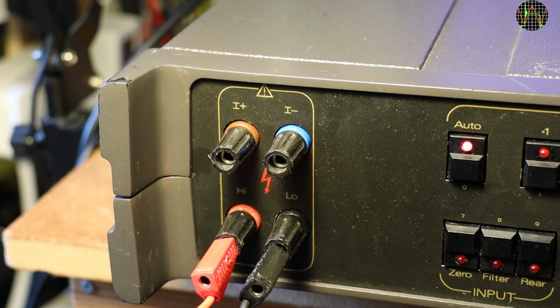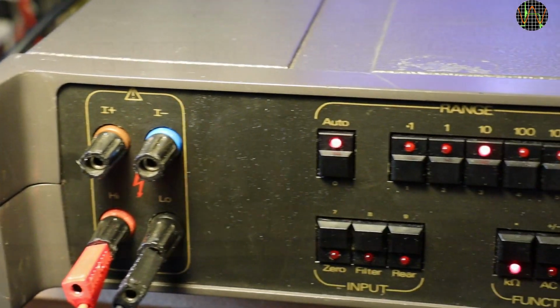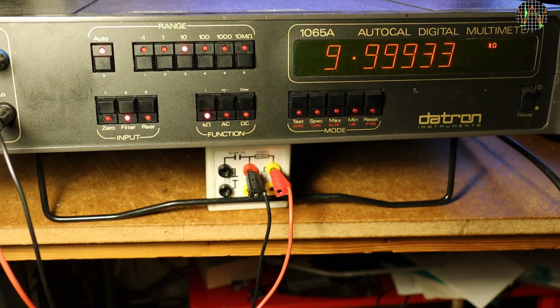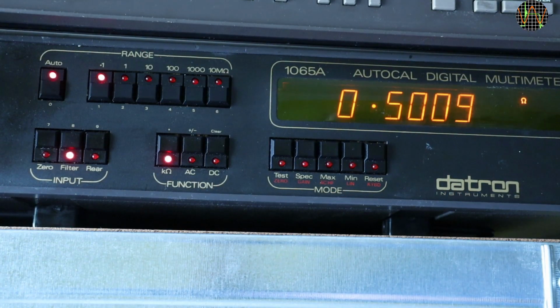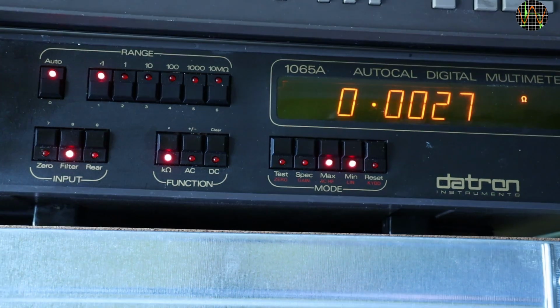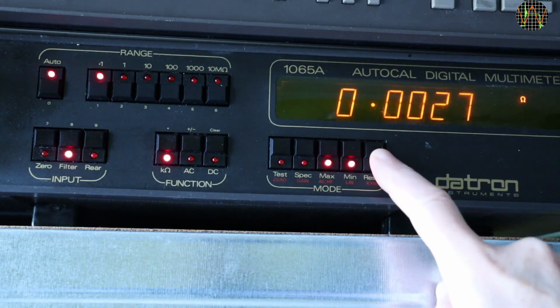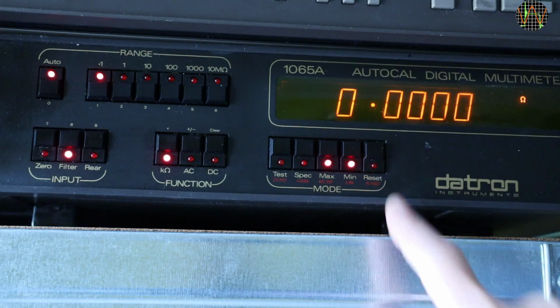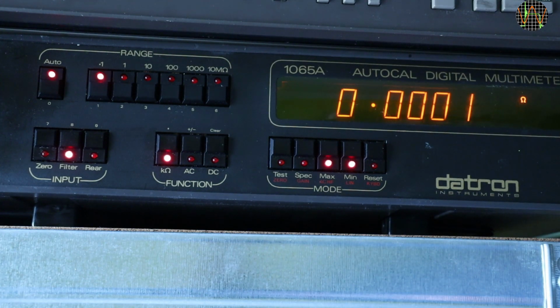These I plus and I minus terminals are only for 4-wire ohms, not for current measurements, as the 1065A cannot measure currents. Here I am using 2-wire ohms. And this is a 0.5 ohm resistor using 4-wire mode. The min and max button do the usual thing, but the 1065A has an interesting mode when both are put on simultaneously. In this case, it shows the difference between max and min, a kind of peak to peak, since the last reset. What it shows here is the drift, not the absolute value of a resistor, in 100 microohms.